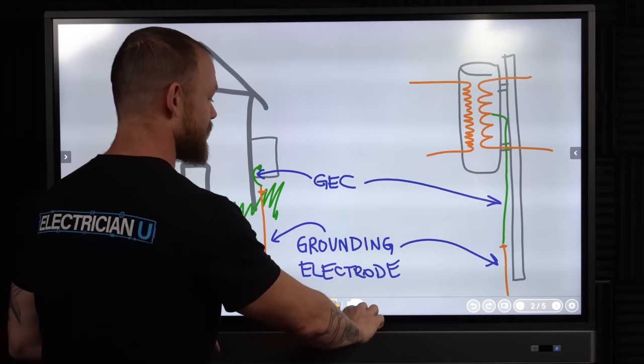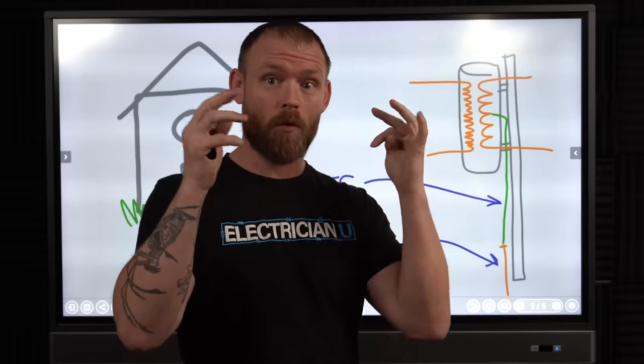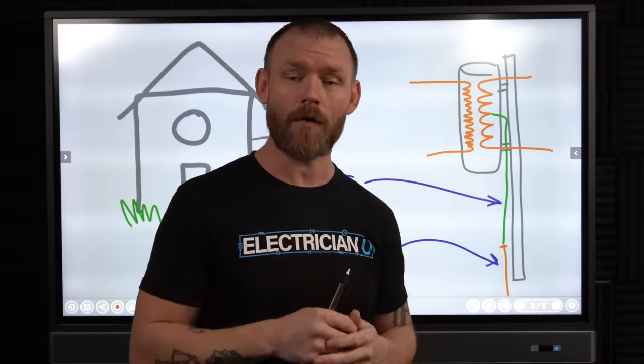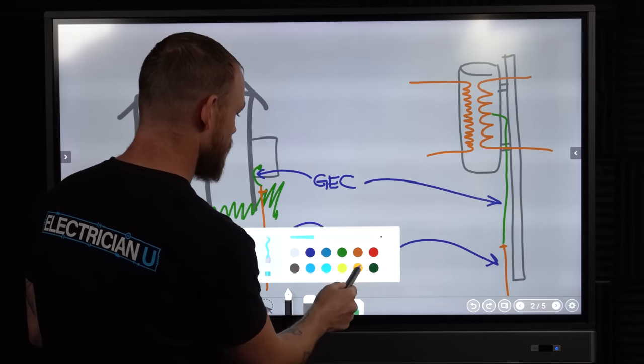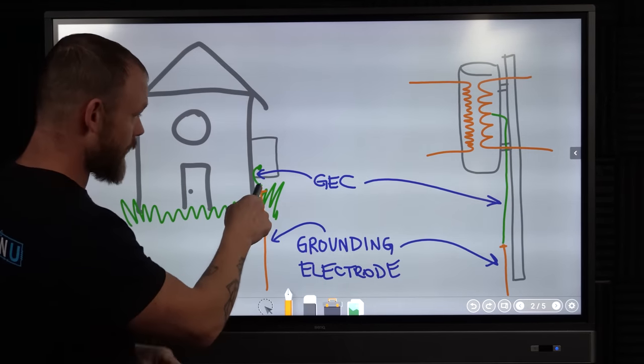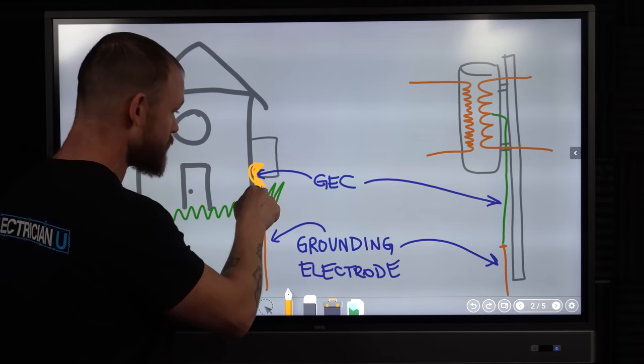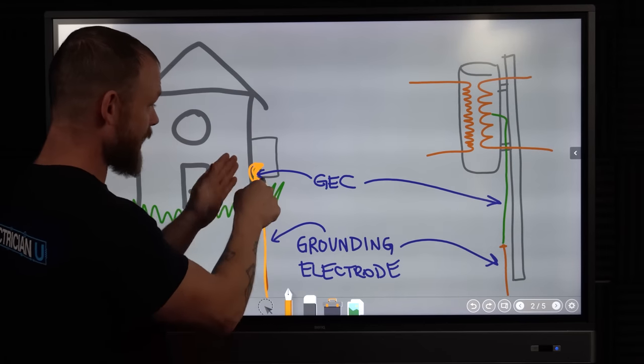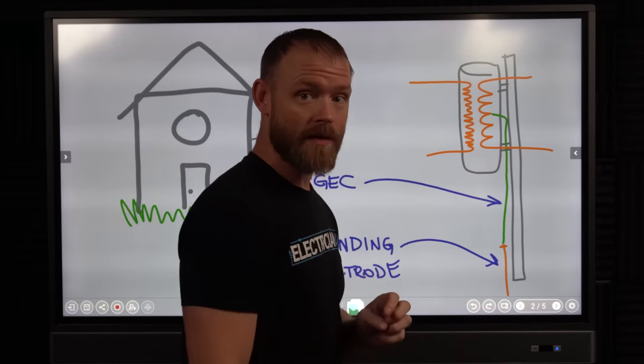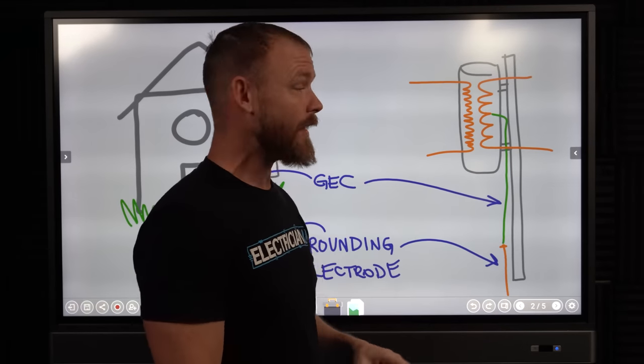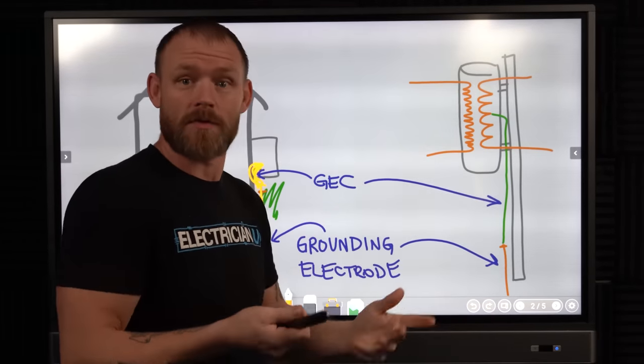The first thing we need to understand is what a grounding electrode is. When talking about a GEC — if you keep seeing people throw that term around — they're talking about a grounding electrode conductor. Specifically, that is the conductor we run to the grounding electrode. We run a conductor from a ground bus down to a ground rod; the ground rod is a grounding electrode, so that conductor in between is called a grounding electrode conductor. Over at a utility pole, same thing — they drive ground rods at the bottom and run a conductor down, intentionally grounding the system.